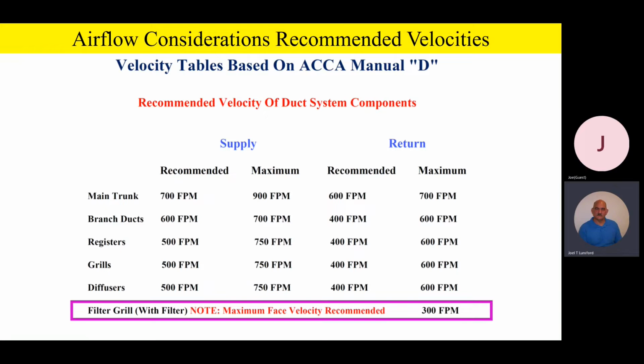If the homeowner or the contractor has installed the equipment with a filter grill, so you've got a return grill with a filter in it, it's recommended that they do not exceed 300 feet a minute velocity across that filter, because if they do, it can cause evaporator issues as far as not being able to absorb the heat properly and so forth. All of this is in Manual D, and it's also part of our airflow and duct design class, which we'd be more than happy to conduct with everyone on this call at some future date.